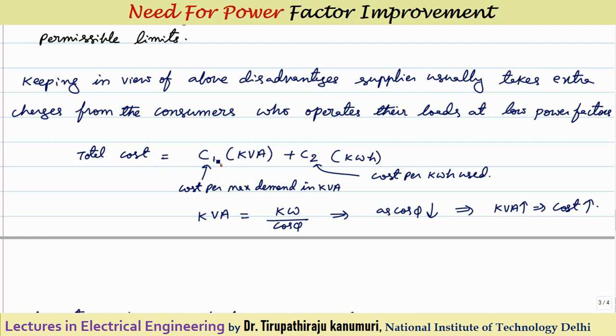For industries, the two-part tariff is: C1 × KVA maximum demand (where C1 is cost per unit of KVA maximum demand) plus C2 × total kilowatt-hours consumed (where C2 is cost per kilowatt-hour). The first term depends on KVA demand. Since KVA equals kilowatts divided by cos phi, as cos phi decreases the KVA demand increases. So consumers operating at low power factor have higher KVA demand and must pay more.